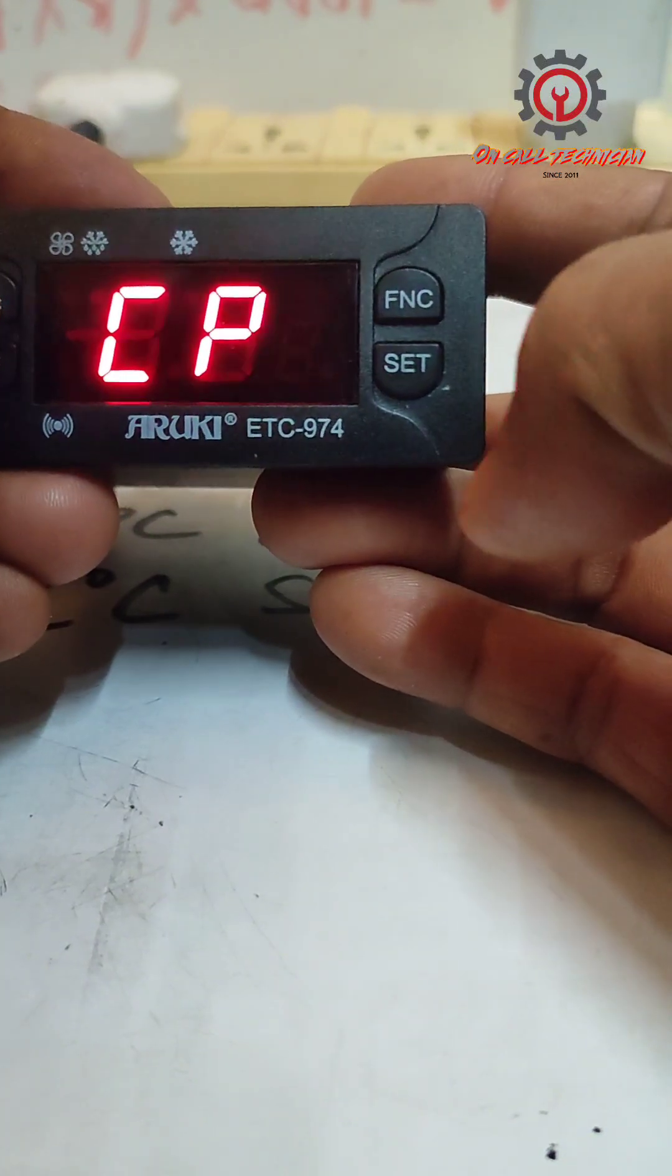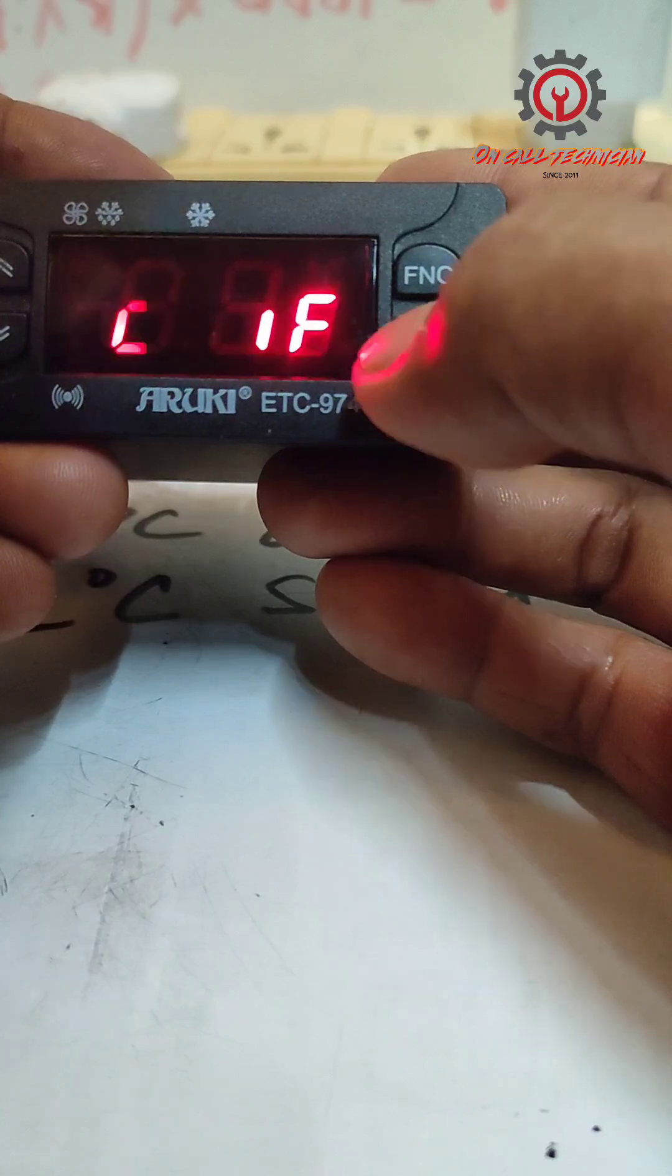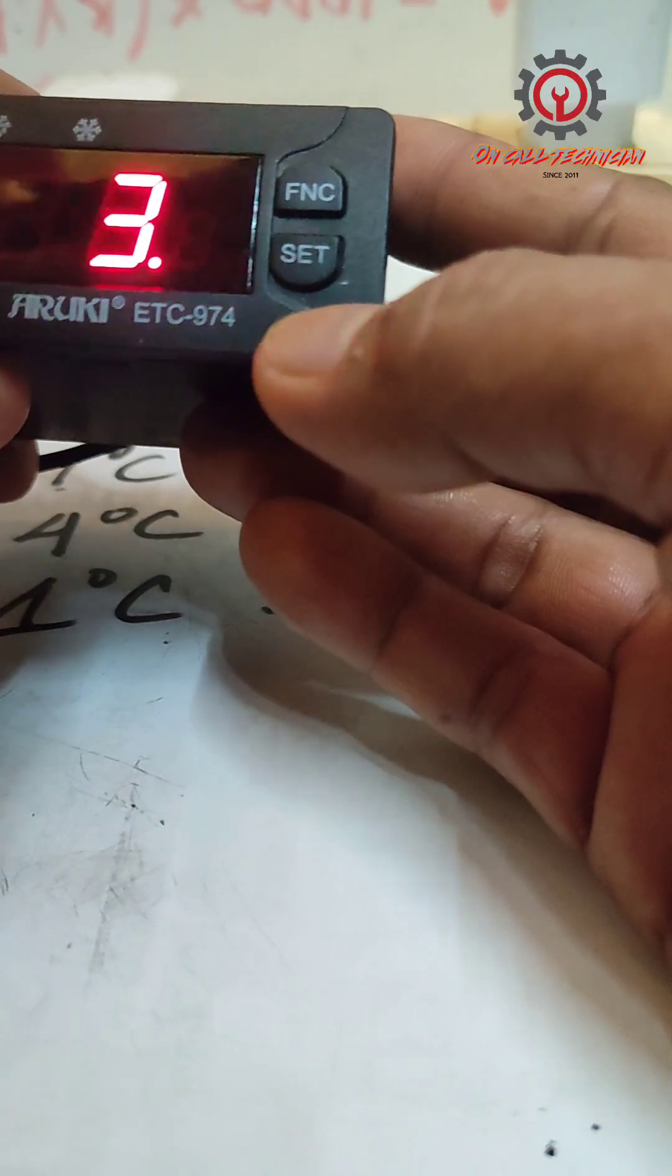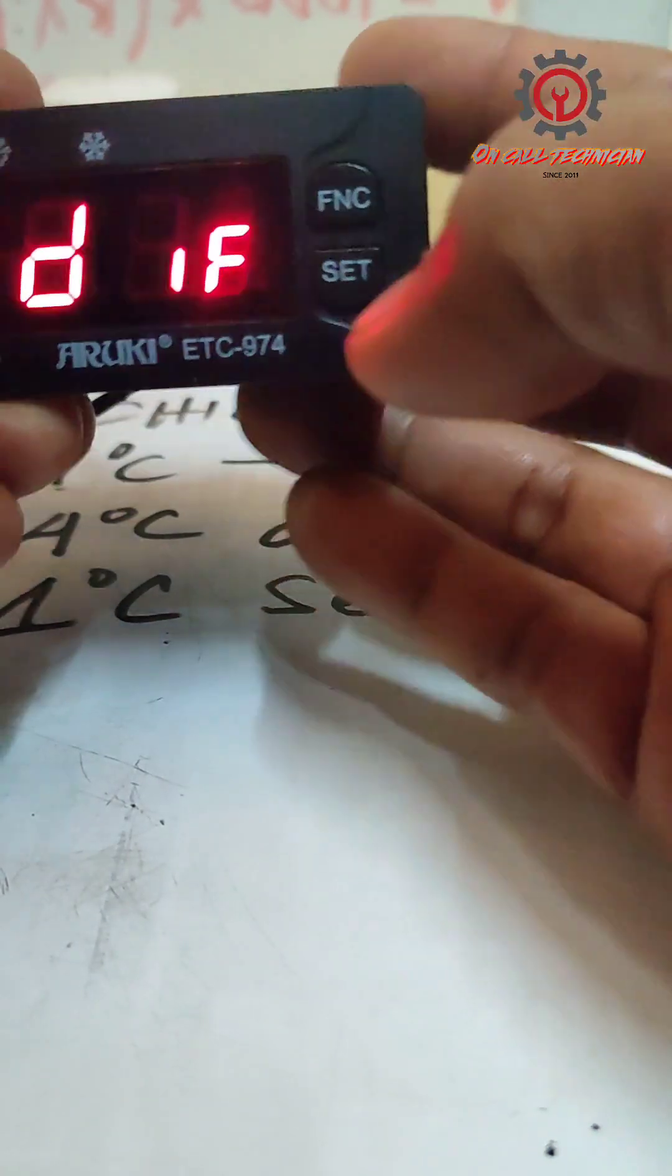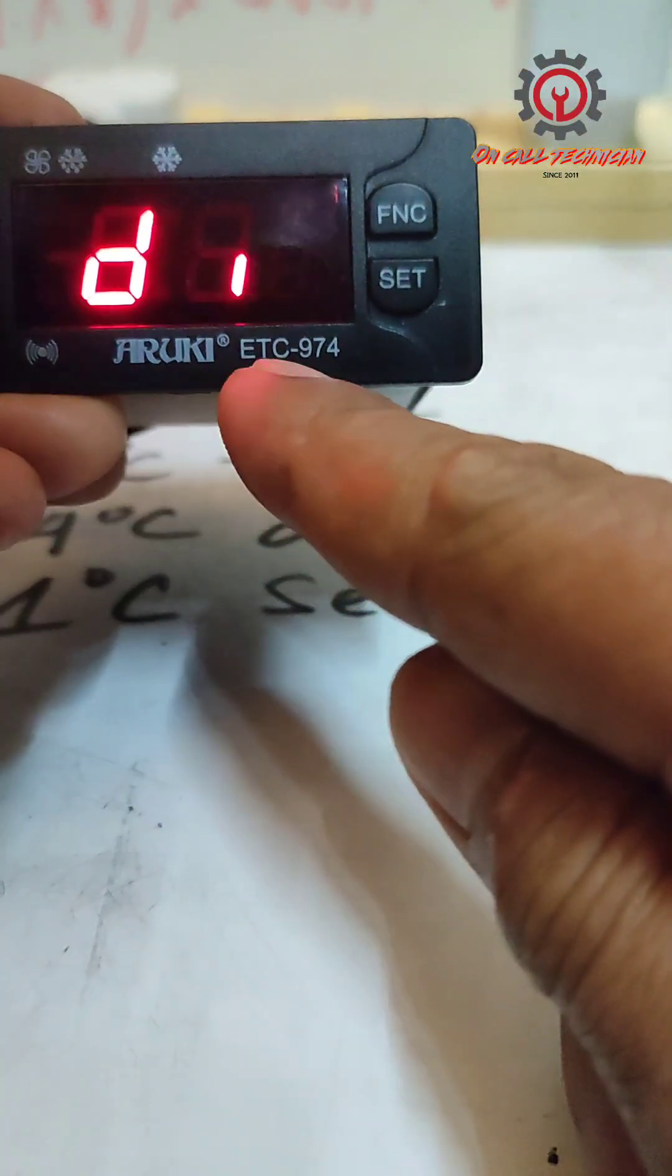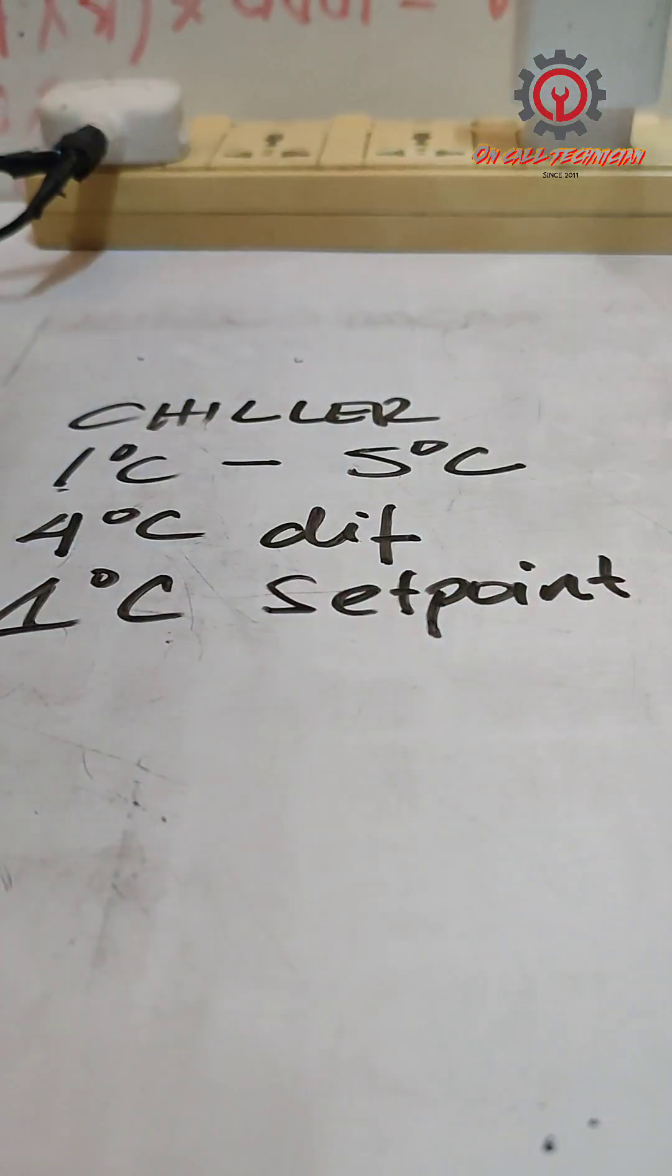Then press set again and the differential will appear. Press it again and we're going to change that into 4 degrees Celsius by pressing the up button, and press set to memorize. This ARUKI ETC-974 is now in chiller setting.